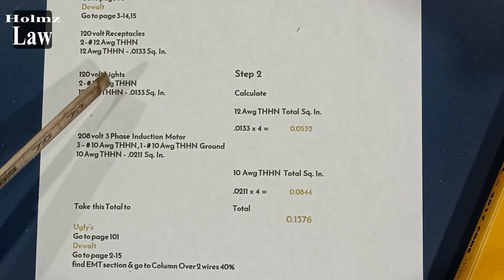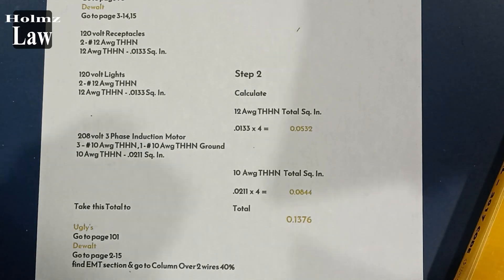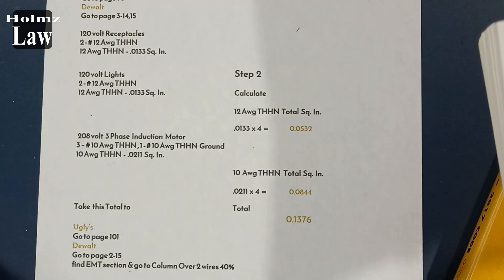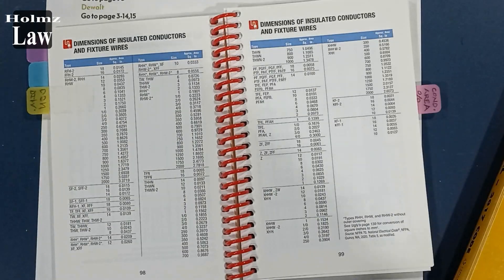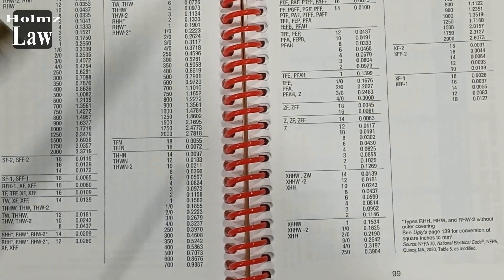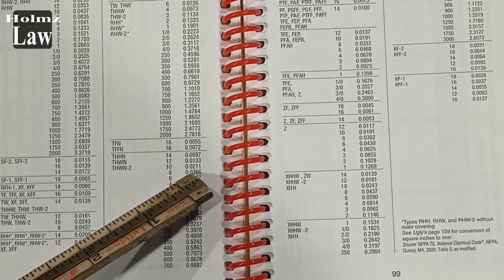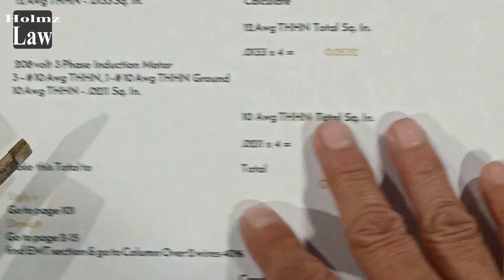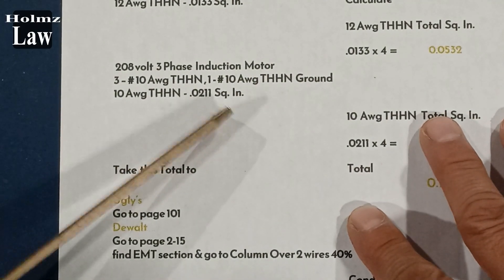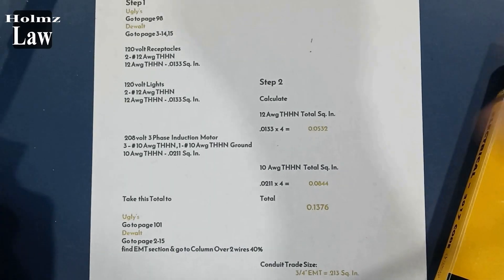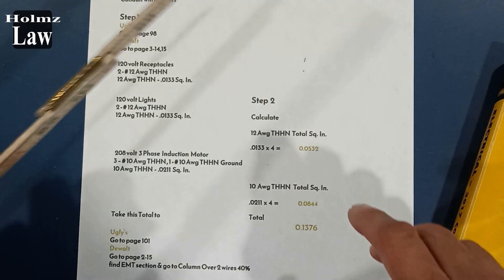If you were using a different insulation type, you'd look that up separately. For the motor circuit, we need the 10-gauge square-inch dimension. On page 98 of the Ugly's, under 10-gauge, you'll find 0.0211 square inches — write that down as well. So now we have our two values: 0.0133 for 12-gauge THHN and 0.0211 for 10-gauge THHN.